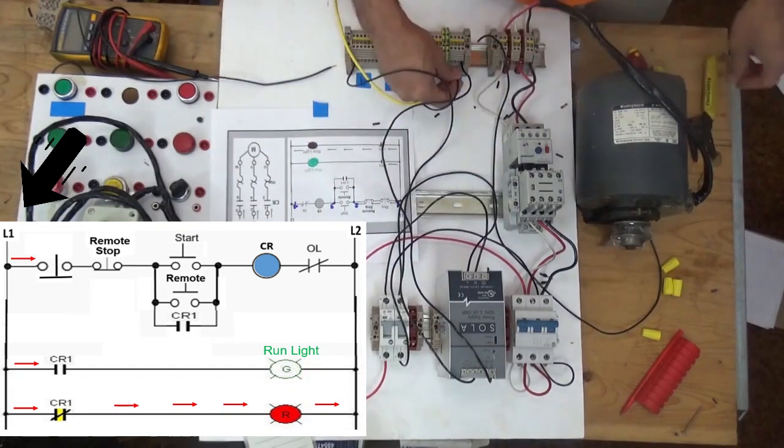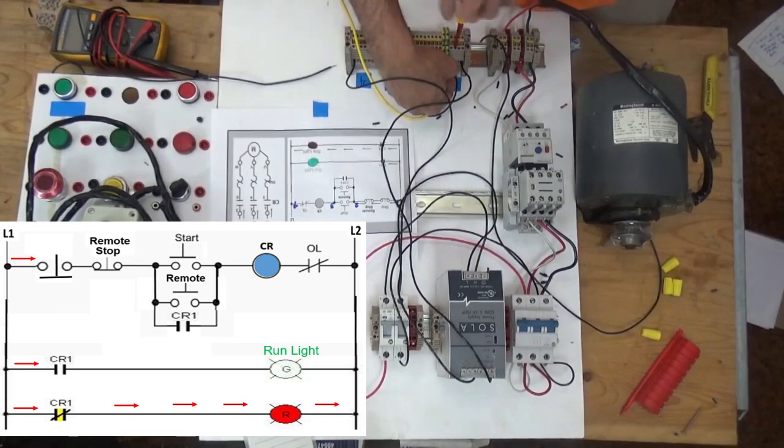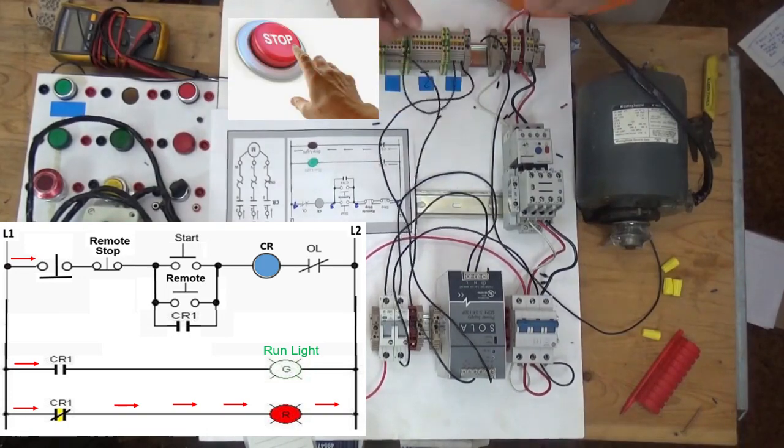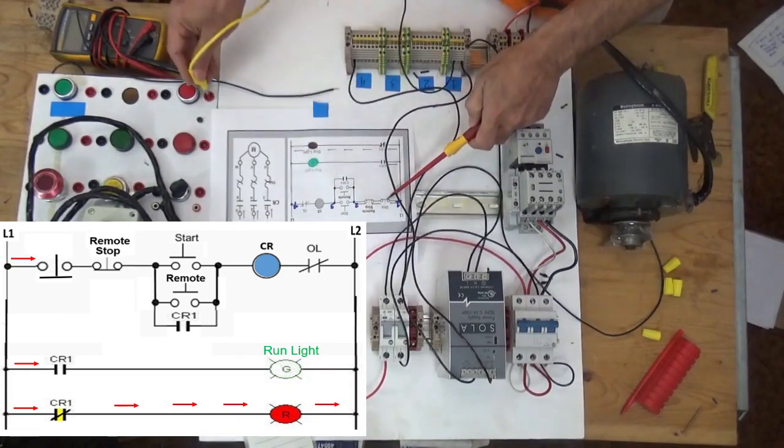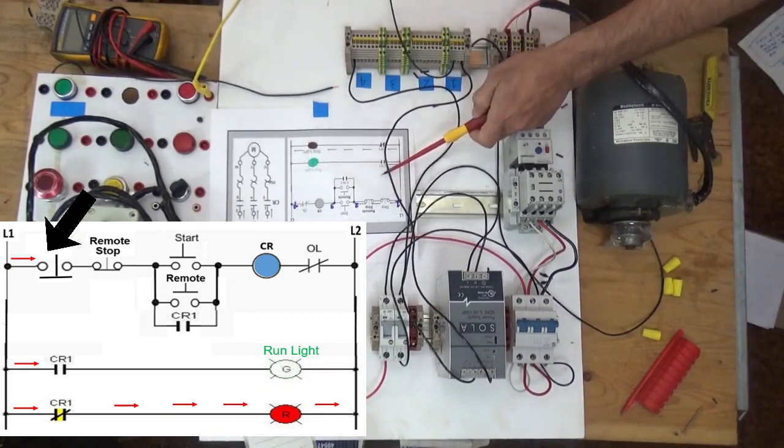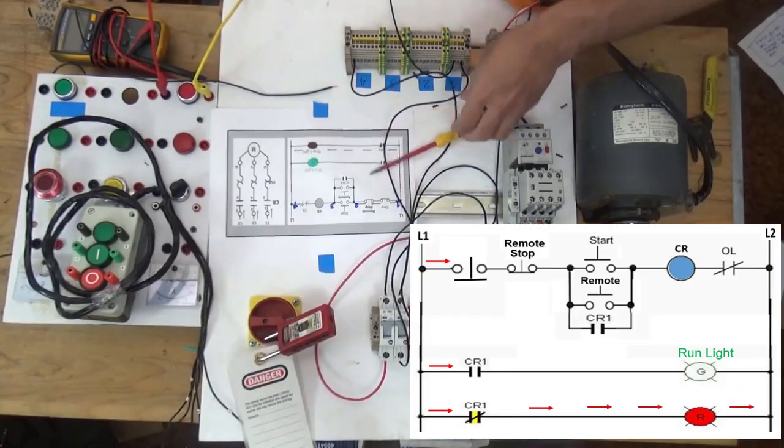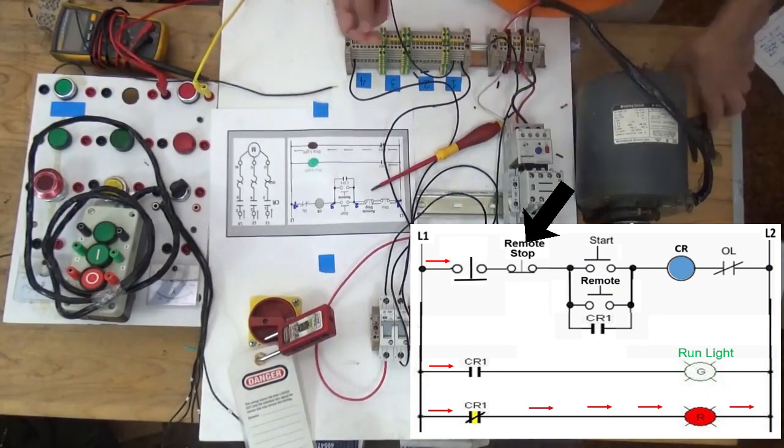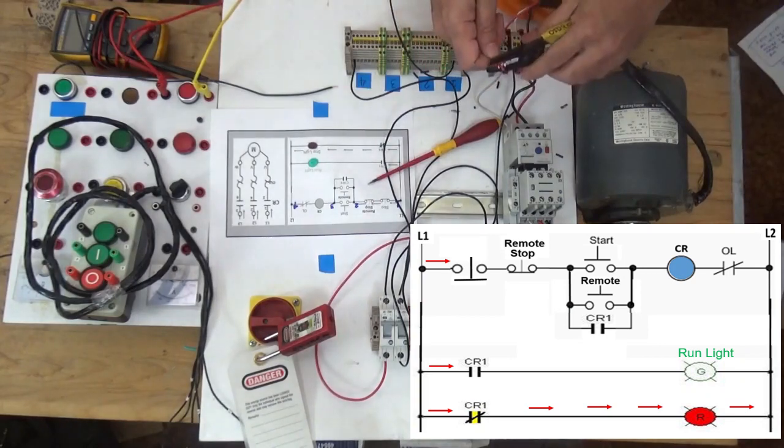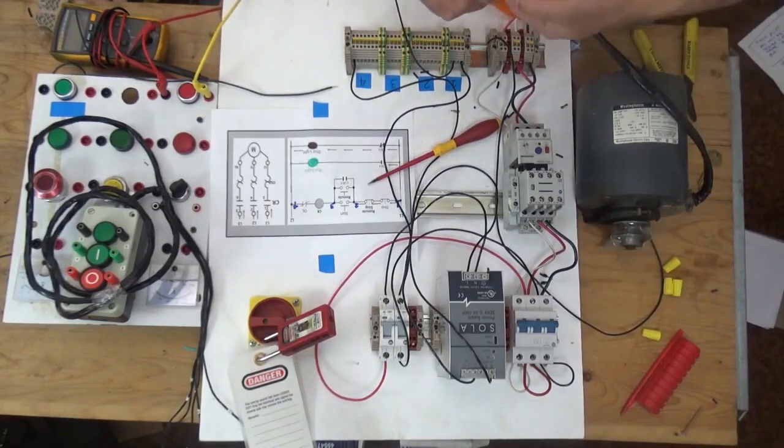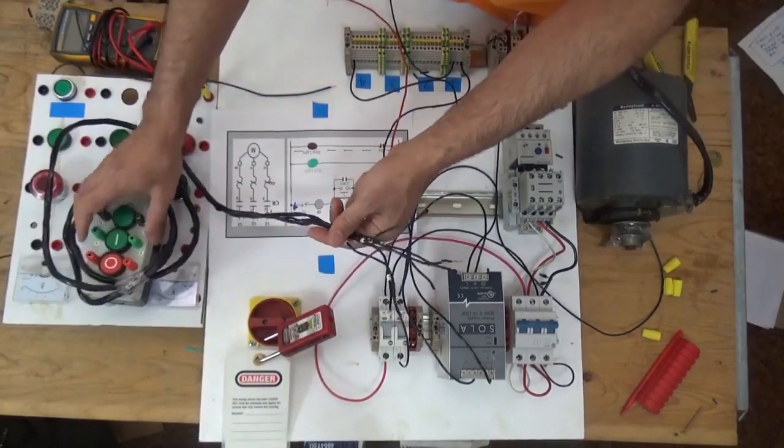So now we already have supply from our 24 volts power supply going to our terminal block. From line 1 here going to our stop push button here. Out of the stop push button going to remote stop push button. The remote stop push button is here.